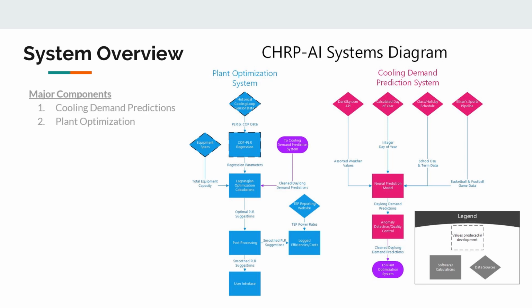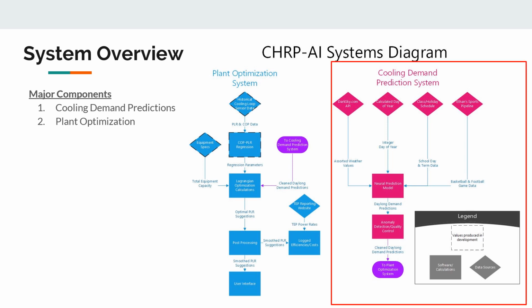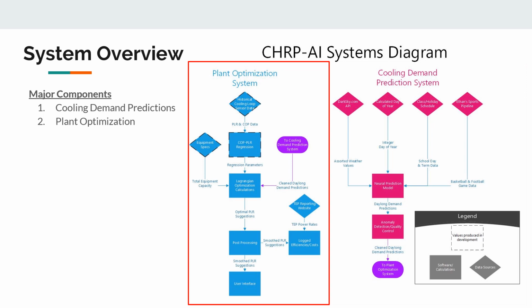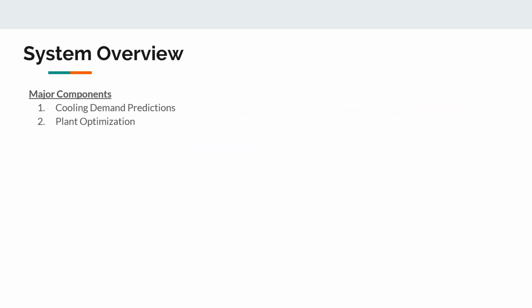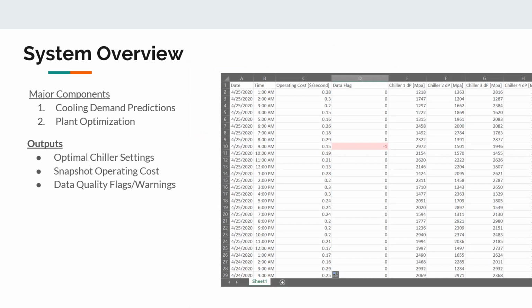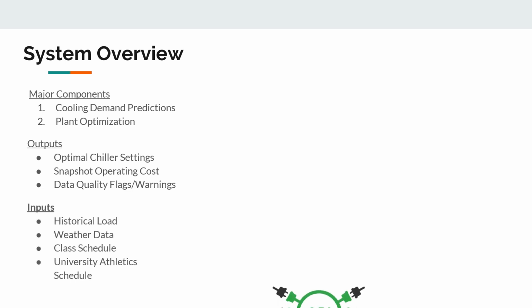There are two main sections of the CHRP-AI system. The first subsystem predicts cooling demand with a selection of data streams, a neural network prediction model, and a quality assurance module. The second subsystem finds the optimal chiller settings using a Lagrangian optimization with consideration for chiller efficiency curves, equipment limitations, and the system provides a CSV of hourly chiller settings with an estimated operating cost rate and flags for any downstream errors. A preloaded model can make predictions in about 7 to 10 minutes on a system with CPU computation only.